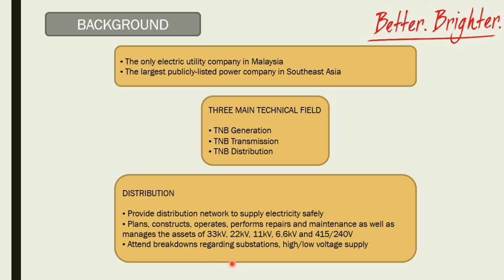The distribution network provides distribution to supply electricity safely. It plans, constructs, operates, performs repairs and maintenance, as well as manages the assets of low voltage supply, which is 33 kV, 22 kV, 11 kV, 6.6 kV, and also 415 to 240 volt. They also attend to any breakdowns regarding substations and low-high voltage supply.